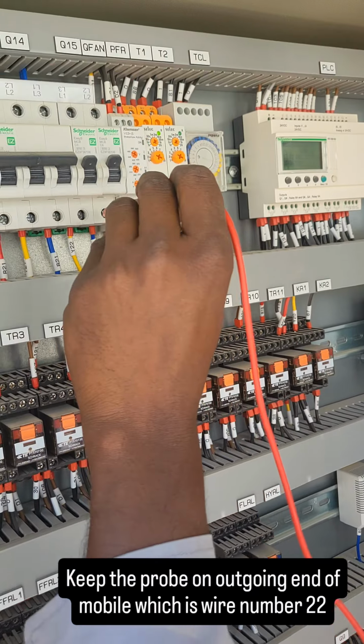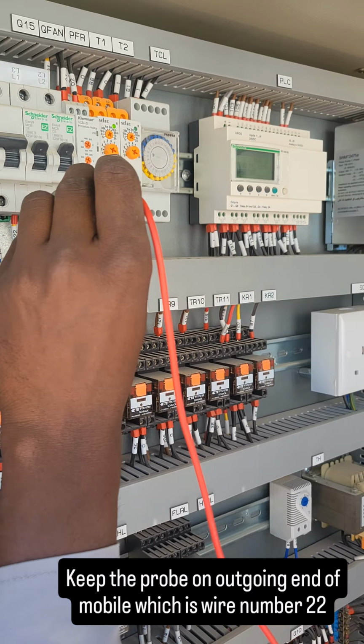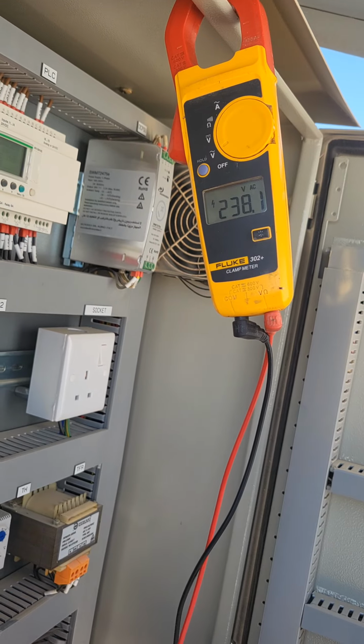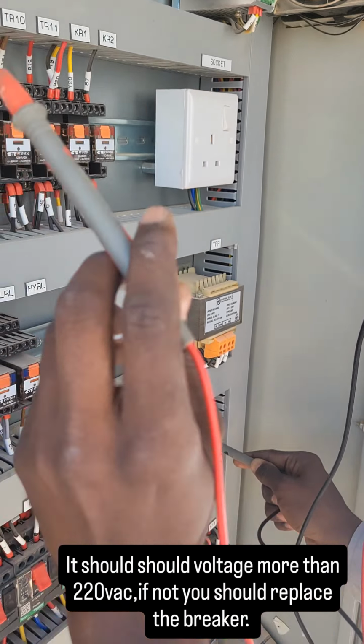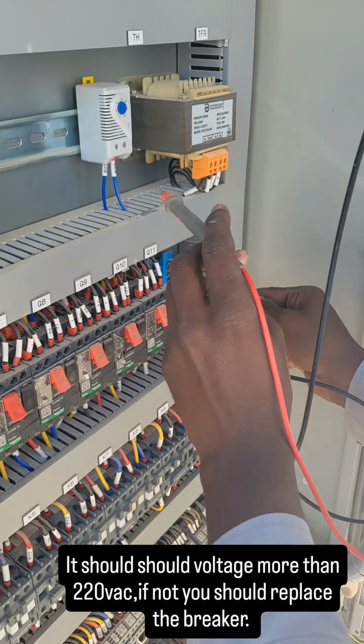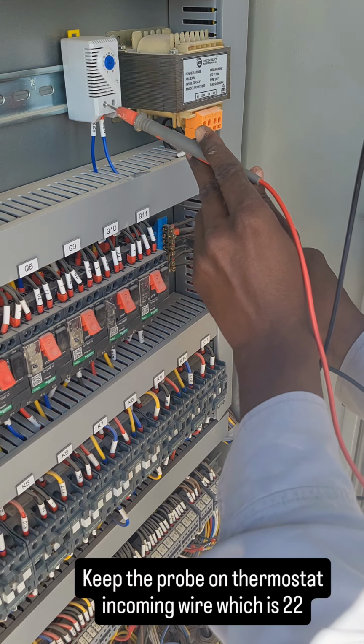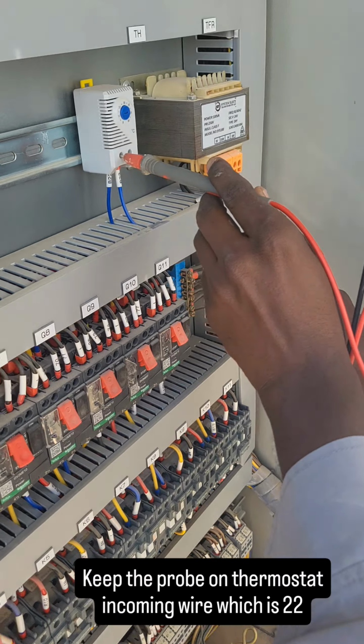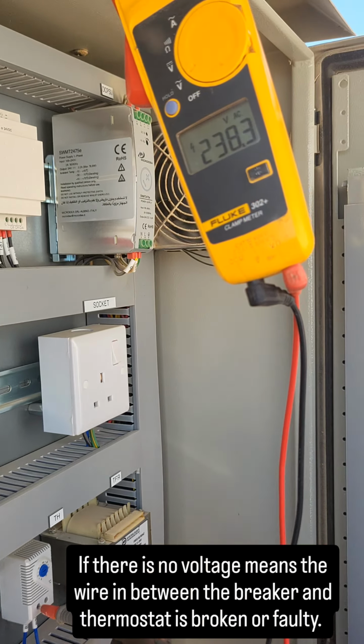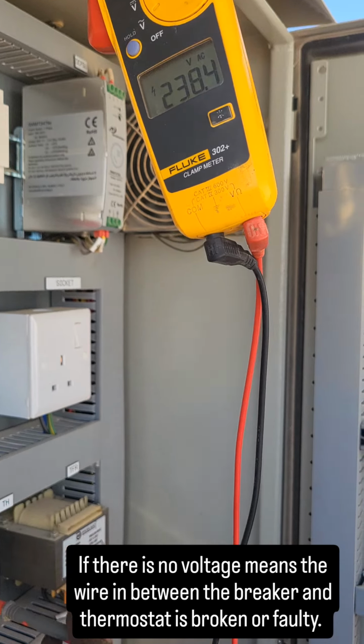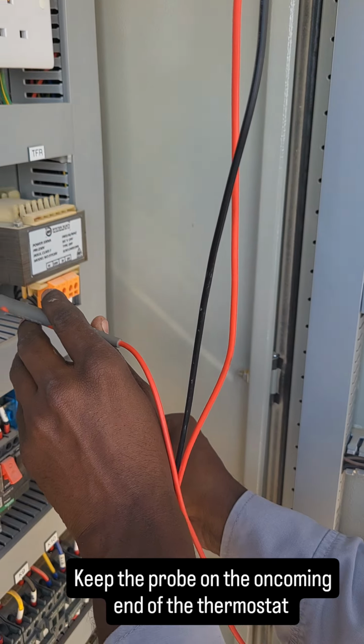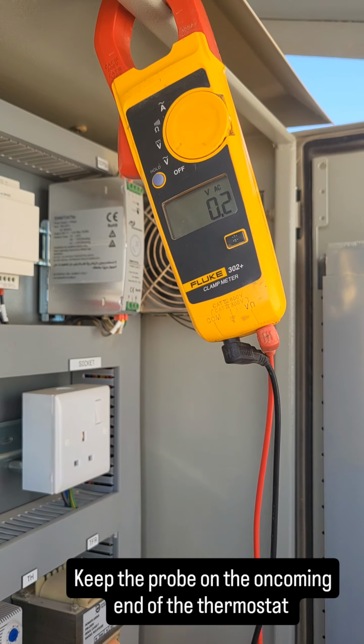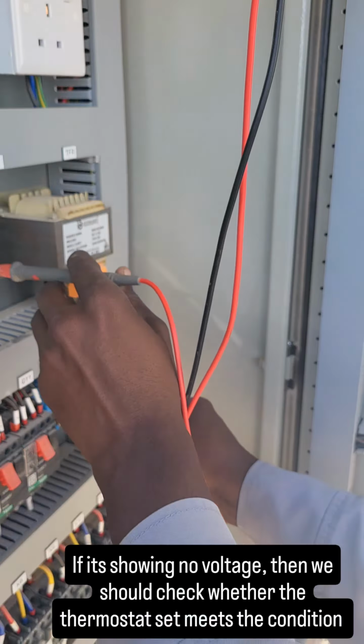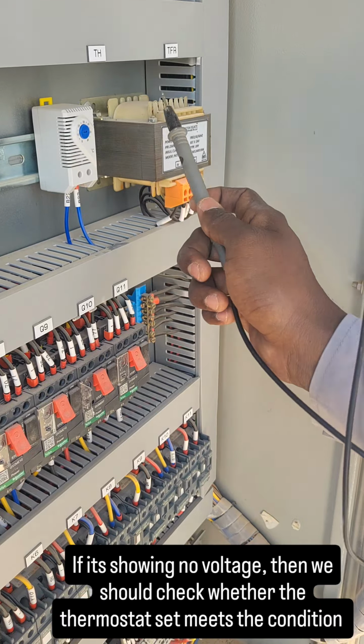Now for the outgoing end of the MCB, the breaker should be turned on. See, now it is good. Now we will keep the probe on the thermostat incoming wire, which is B22. Now it should get voltage if the circuit is good. Yeah, it is getting voltage. Now keep the probe on the outgoing of the thermostat. So here there is no voltage, so the thermostat is not becoming NC.